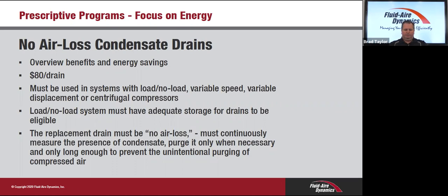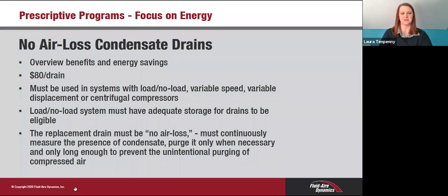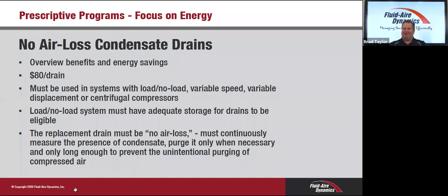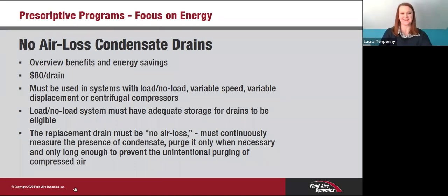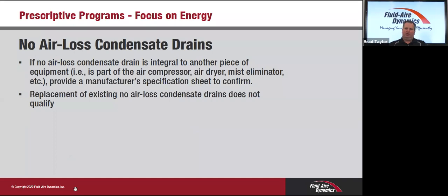Anything else you can add to that, Laura? No, just that it's very common to have those old timer drains, and those are just timed leaks, and we hate leaks. So if you can not waste any of that compressed air, it's just going to save in the long run. Well, you mentioned timer drain. At least that's better than the drain valve half cocked open. That is true. But yeah, they're paying about 25% of a good zero loss drain valve. So it's a good incentive, especially when you bundle it with a compressor installation or a leak repair. It's a no-brainer.